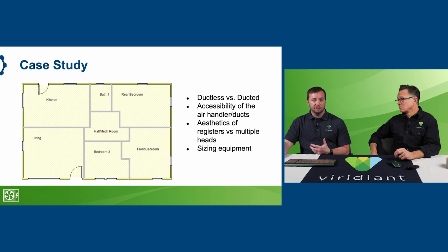Personally, I'd probably be leaning towards 5 heads. The smallest capacity for most manufacturers is 9,000 BTU. For some, you can find 6,000 BTU. If you end up going with that standard 9,000, then you've installed 45,000 BTU of capacity, which, having done a manual J calculation, is over twice what's needed. While the equipment is variable capacity, it's a whole lot of extra capacity that the homeowner has to pay for. It also introduces a problem of likely not having enough moisture removal ability.